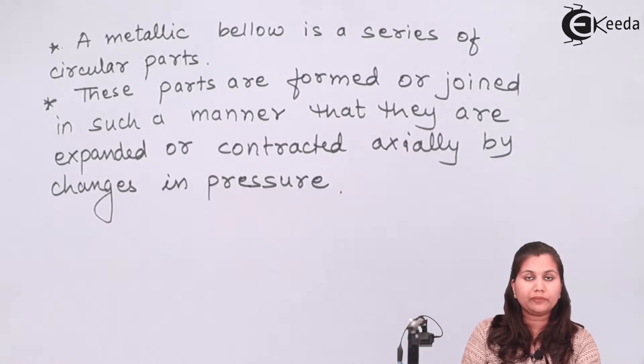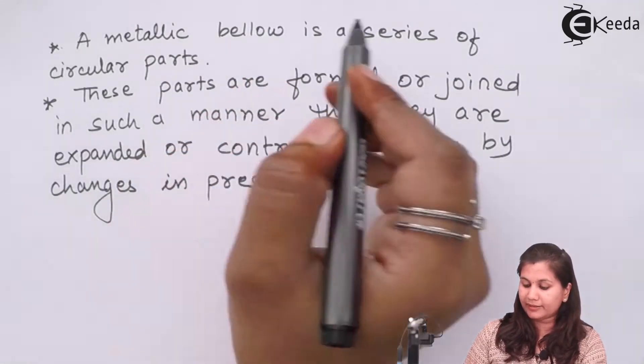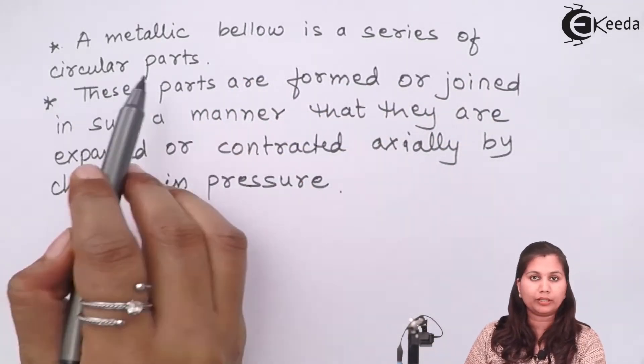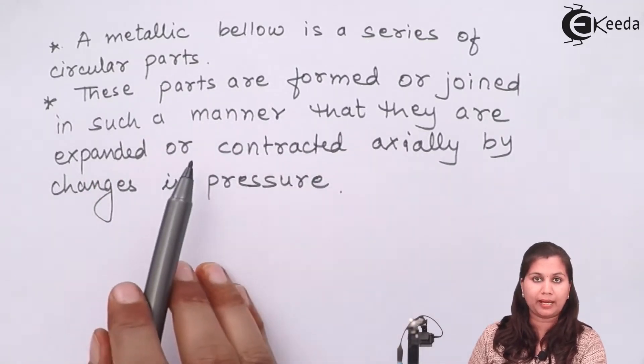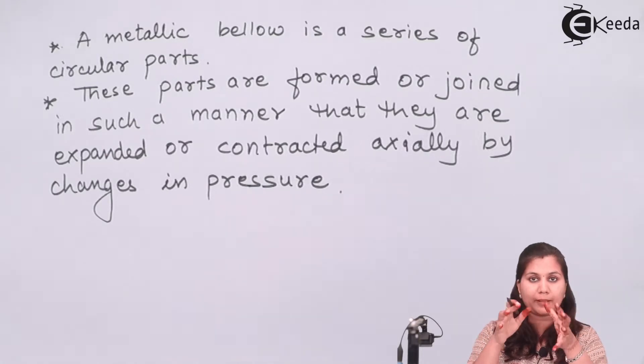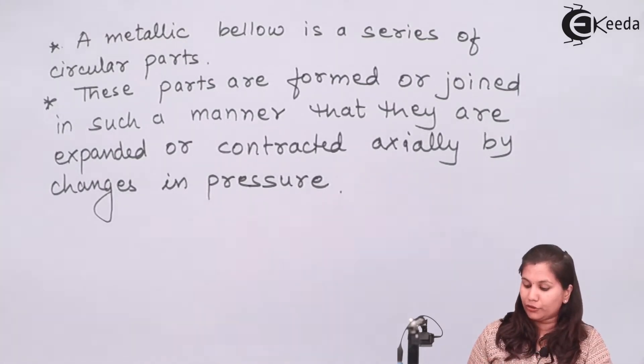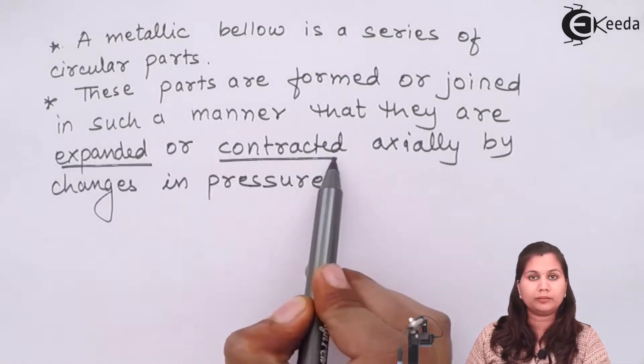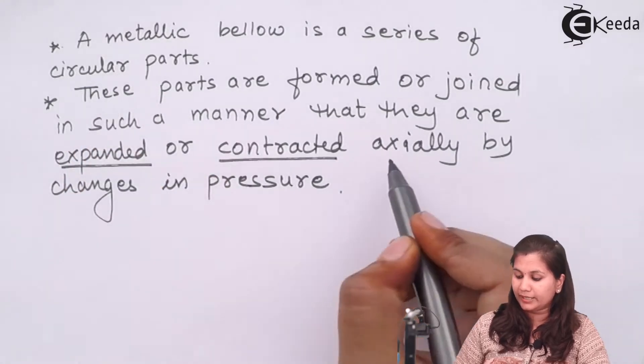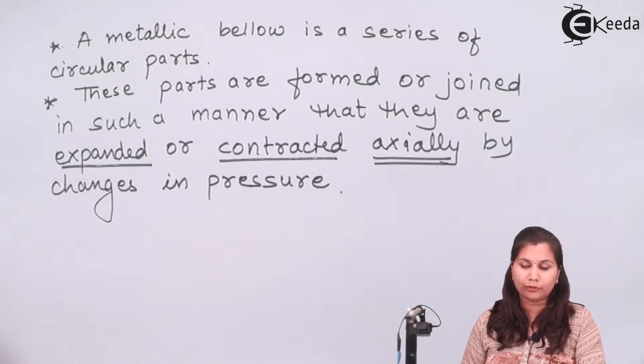Now comes the construction of the bellows. The bellows are a series of circular parts, and these circular parts are formed or joined in such a manner that they are going to expand or contract when the pressure is applied to them. When pressure is applied on the bellows they are going to expand, and when the pressure is released they are going to contract and come back to the earlier shape. The expansion and contraction of the moving parts or the circular parts is in the axial direction. Let's see the diagram of a bellows.